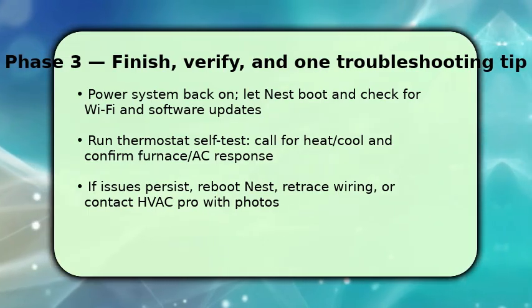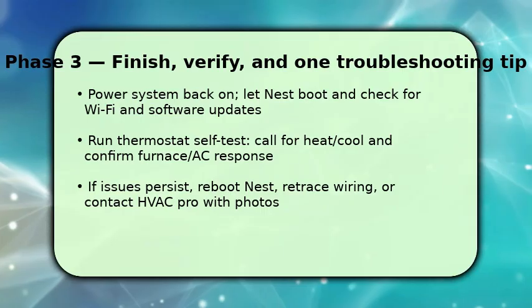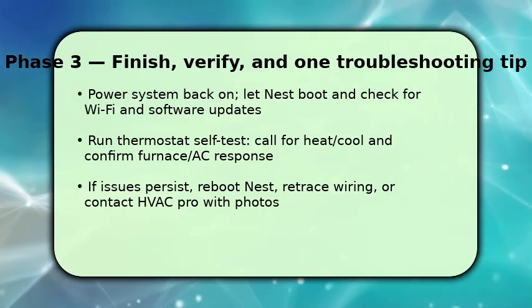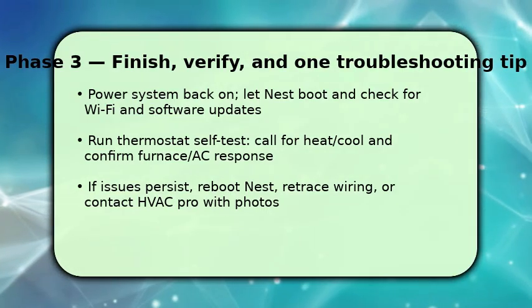Then run a manual call for heat and cool to confirm the furnace and AC respond. Watch the system at the equipment to ensure relays and fans engage.